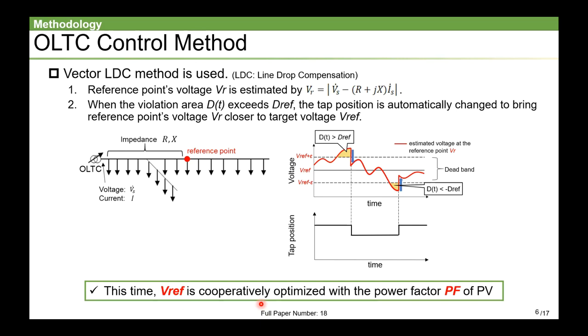In this slide, I want to explain vector-LDC control method that we adopted as the control method for OLTC. In this method, the voltage of the reference point Vr is estimated by this equation. And then, when the area of violation from Vref plus minus epsilon exceeds the Dref like this, the tap operates to bring Vr closer to Vref. There are many parameters in the vector-LDC method, but in this study, we will optimize Vref with the power factor PF of PV inverters.